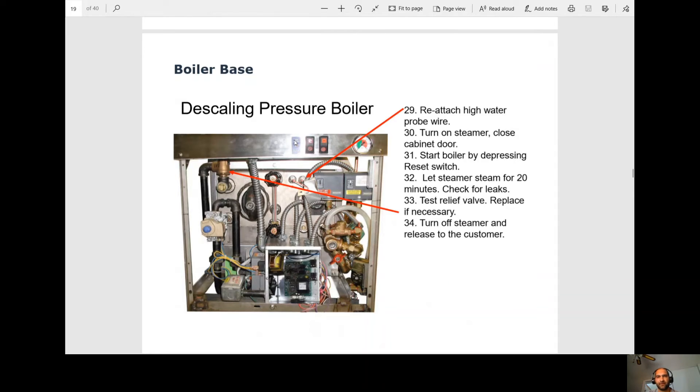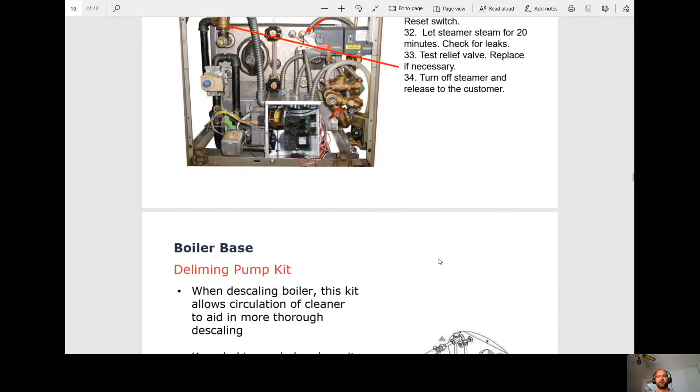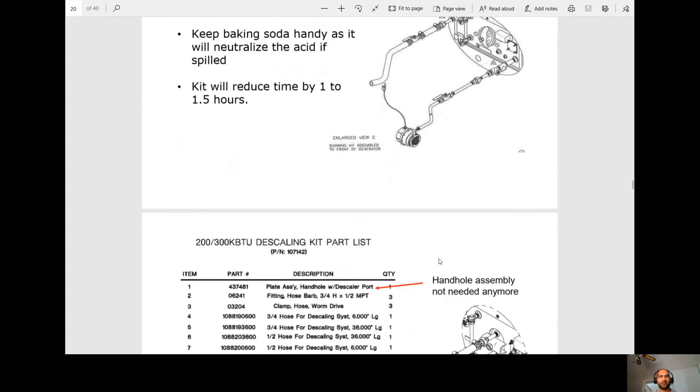So once the boiler fills, the reset light is going to come on. You're going to click the reset switch. Now we're going to steam it for 20 minutes. We're going to check for any leaks. We're going to test the pressure relief valve right here. That needs to be tested every time we descale the boiler. At that point, once the 20 minute steam is done, turn off the steamer and that's the end of the process.